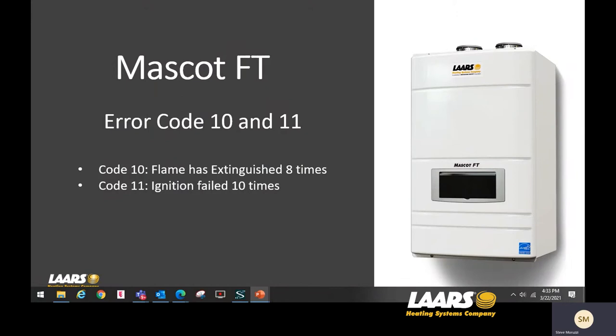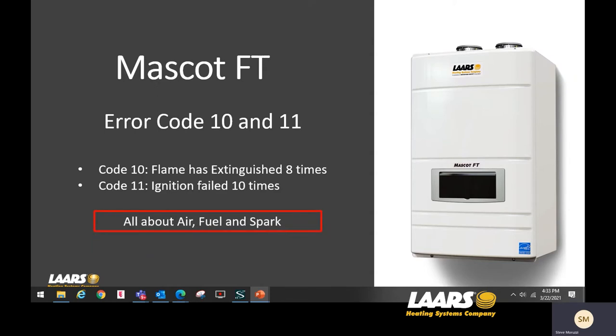We'll start with error code 10 and error code 11. Error code 10 is the flame has extinguished eight times. Error code 11 is ignition failed 10 times. It's all about air, fuel, and spark.